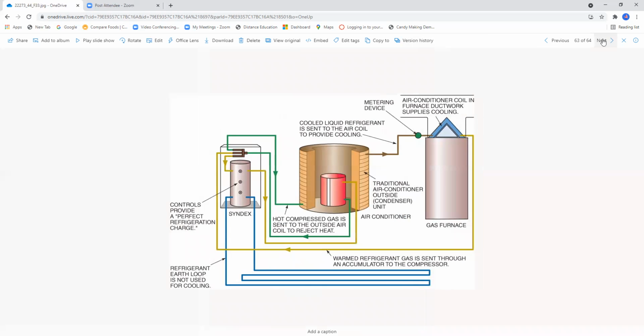Okay, in this illustration right here, we have a gas furnace, and then we have an air conditioner. This is an illustration on page 1345. This is a cooling mode schematic showing how this unit works. It basically controls the flow to make sure that we have enough refrigerant flowing. So basically this is a large reservoir. You have your 3 sight glasses. Here you have the air conditioner, the traditional outside condensing coil. And of course you've got the evaporator coil up here, the metering device. And then we have the ground loop.